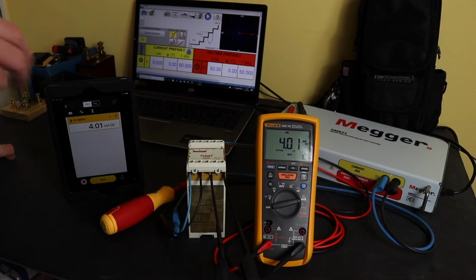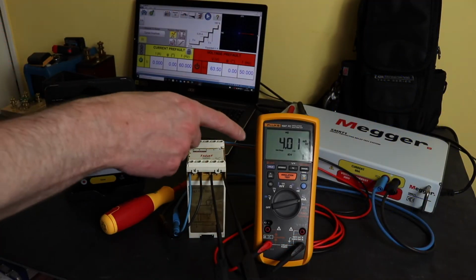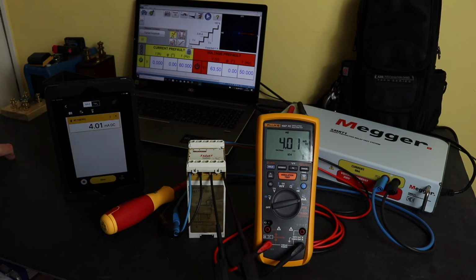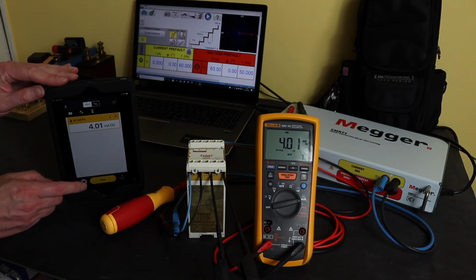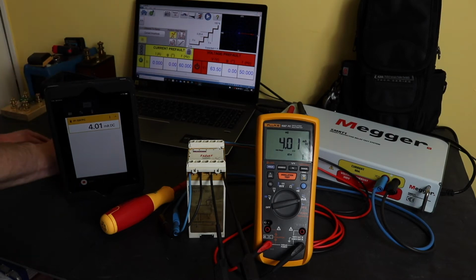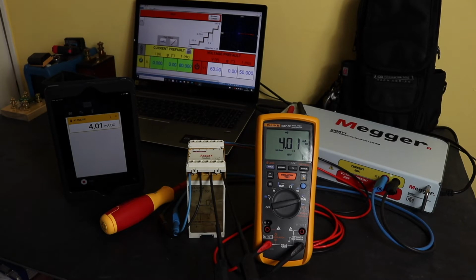So you see at the moment the transducer is just energized. It's kicking out 4 milliamps with no input onto it whatsoever. So we will press record on the laptop and we set the SMRT1 running, and I should be recording the results.